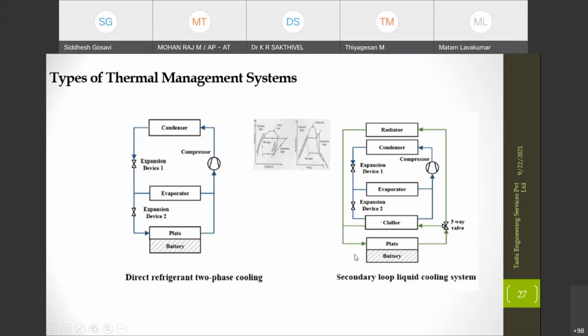So one of the advantages in this method is that it's very flexible, as we can see, because in case I don't want this evaporator to be functioning, or in case I don't want my chiller to be active, I just have to shut down this one, whereas I can continue using the evaporator as well. Also, the same water ethylene glycol I can pass into my motor cooling unit, power cooling unit as well. And if I have to heat the battery pack, that will be the case in most of the cold countries, I don't have to turn the compressor on. I just have to heat the chilling mixture.